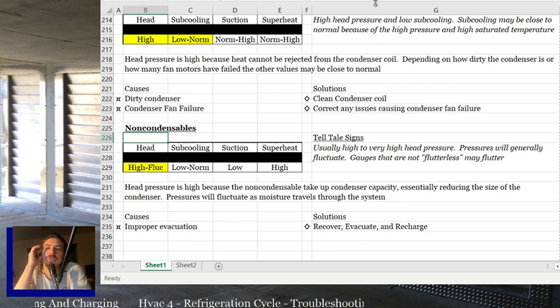The pressures will fluctuate as moisture travels through the system. Cause: improper evacuation. Pull out the refrigerant and try once more, because whoever did it last didn't do it right. So look for the pressure fluctuation more than anything else. And if you don't know how to check for non-condensables in the system, pump it into the outdoor unit, disable your compressor, power your condenser fan. If your saturated temperature does not equal outdoor temperature after about 10 minutes of just the condenser fan running and not the compressor, then the refrigerant in there is not all refrigerant.